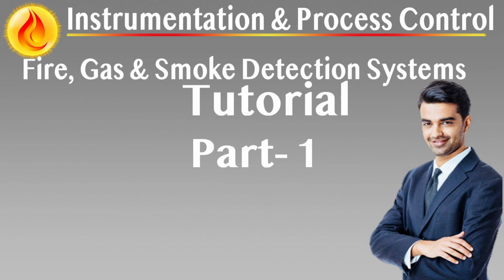Catalytic type detectors. Legacy technology with application caveats. Catalytic Pellistor gas detectors detect flammable gases by catalyzing oxidation on a heated bead, producing heat that unbalances a bridge circuit. Though historically widespread, their use is now conditional and increasingly limited due to significant operational drawbacks. Limitations and risks. Oxygen dependency: cannot detect in oxygen-depleted environments, leading to hazardous underreading.